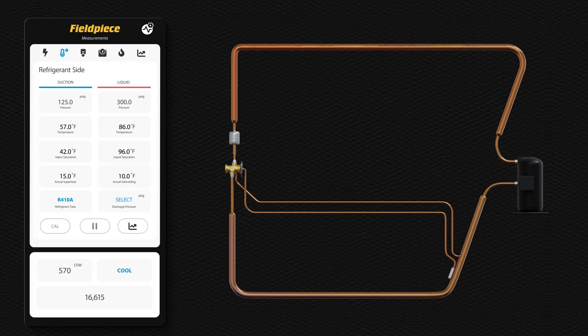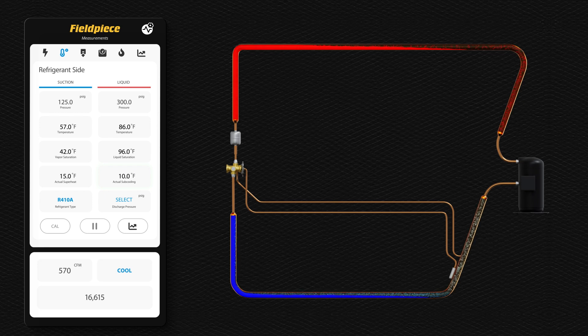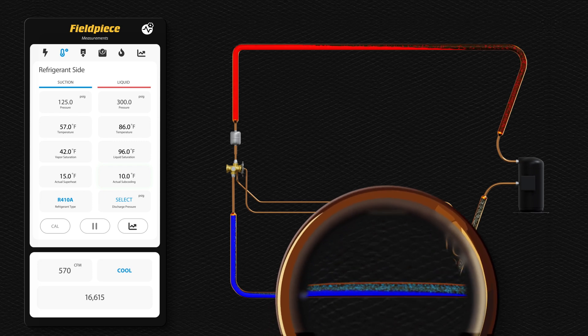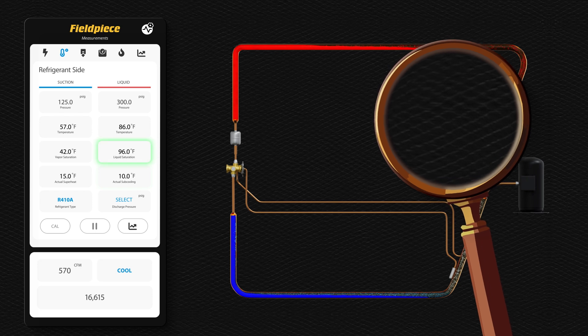The Fieldpiece app shows the saturated condensing temperature equals 96 degrees Fahrenheit. In the condenser, whenever vapor and liquid exist, the refrigerant temperature will be 96 degrees. Any heat removed will only assist in a phase change from vapor to liquid, but the temperature will remain 96 degrees.